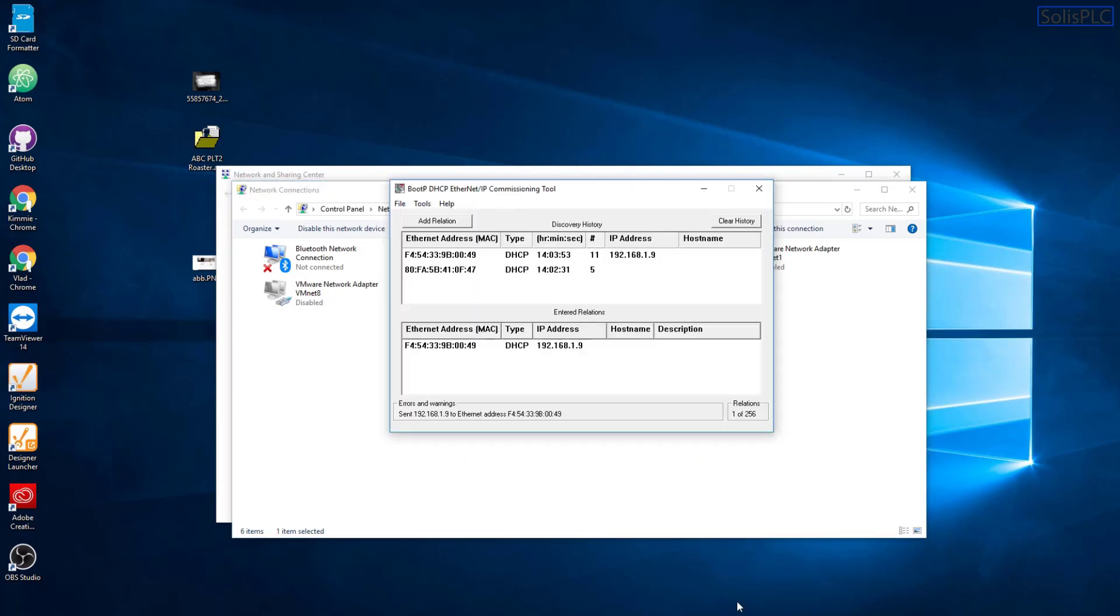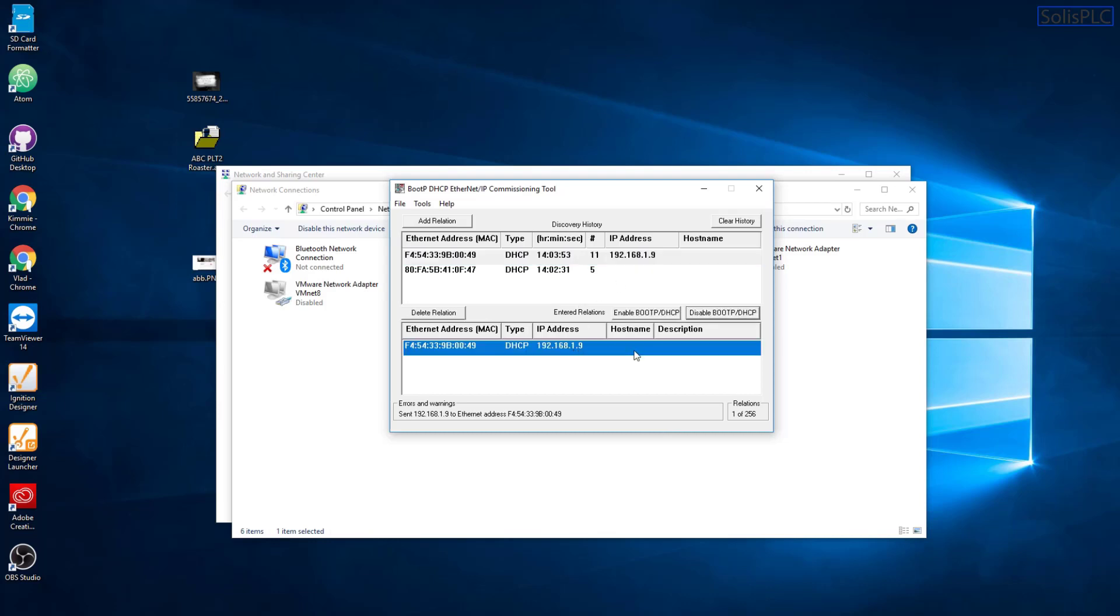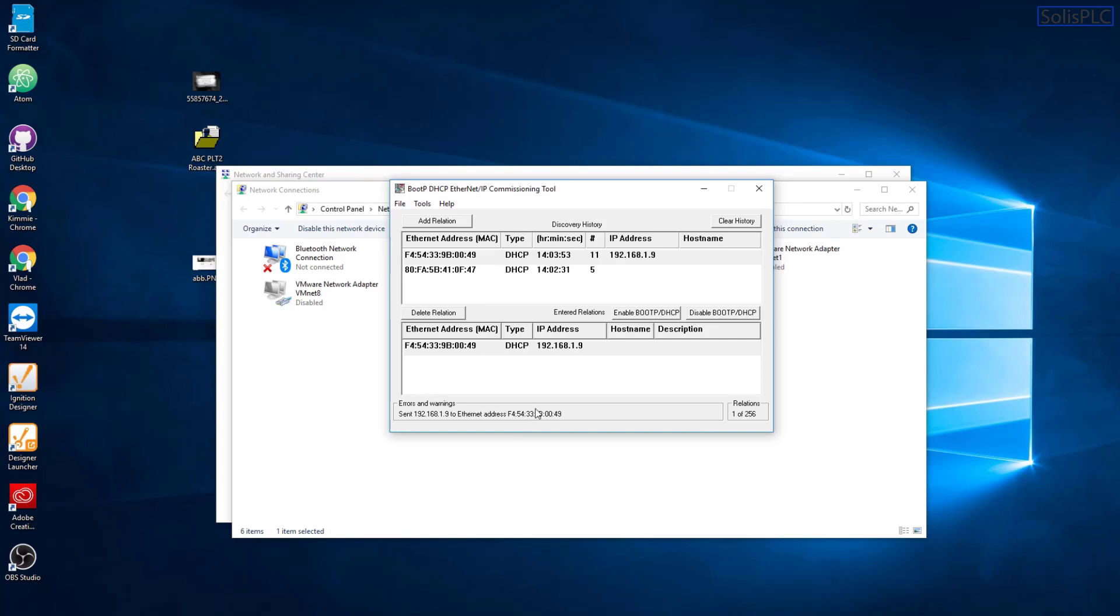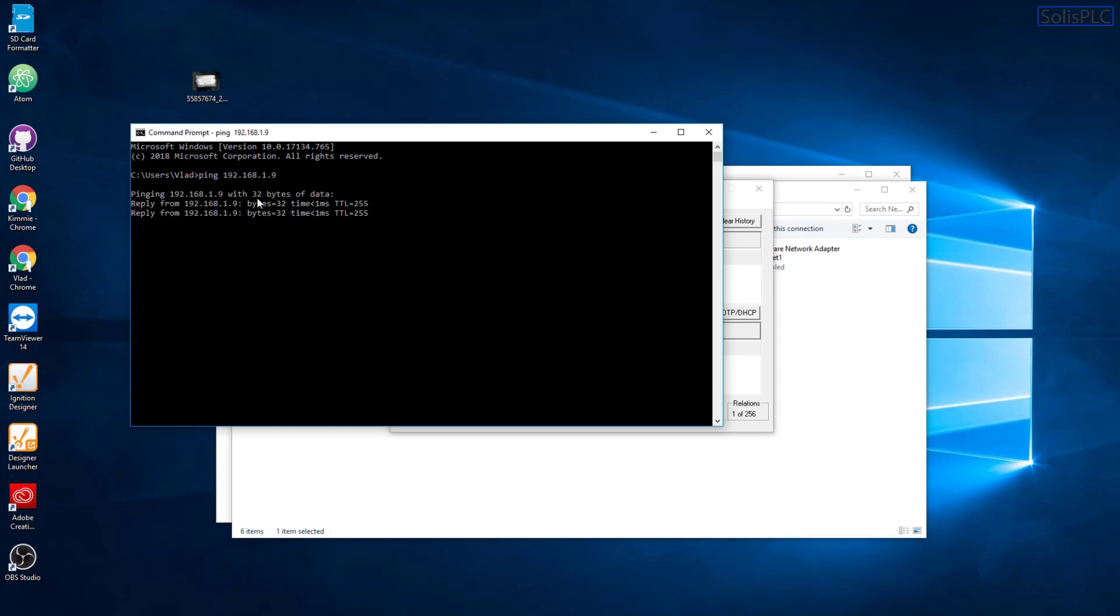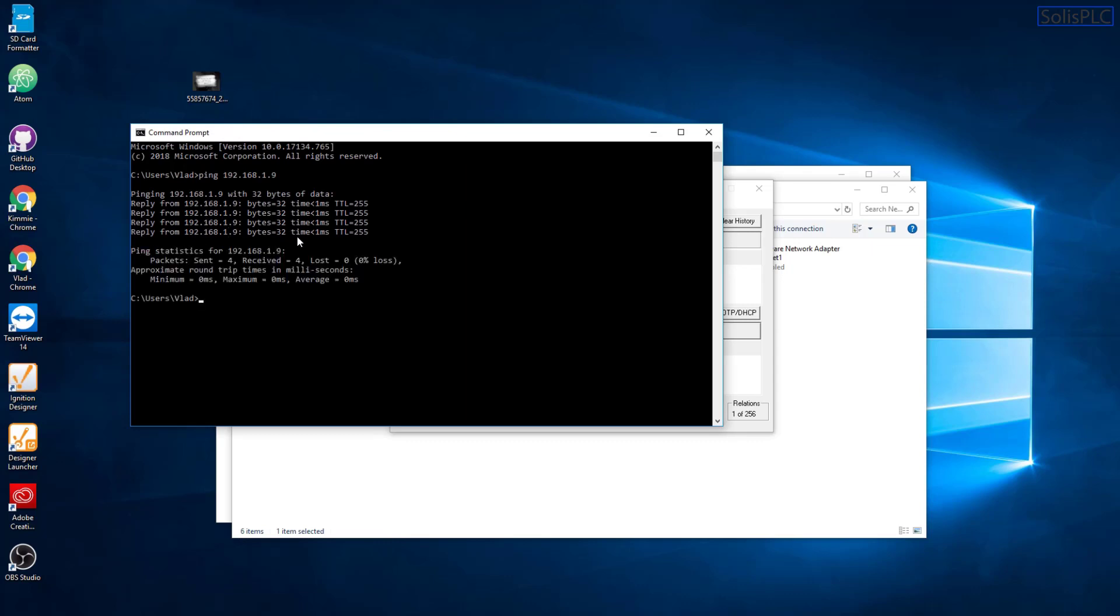And let's go back into the BootP tool. And you'll notice that it did take the IP address. And what we can do here is we're going to click this Disable. And you'll notice that the Sent message is being confirmed, that everything has been taken by this PointIO rack as expected. And it now has the IP address of 192.168.1.9. The way we can verify this is we can go into our command prompt, type in ping 192.168.1.9. And as you can see, the module responds as expected.